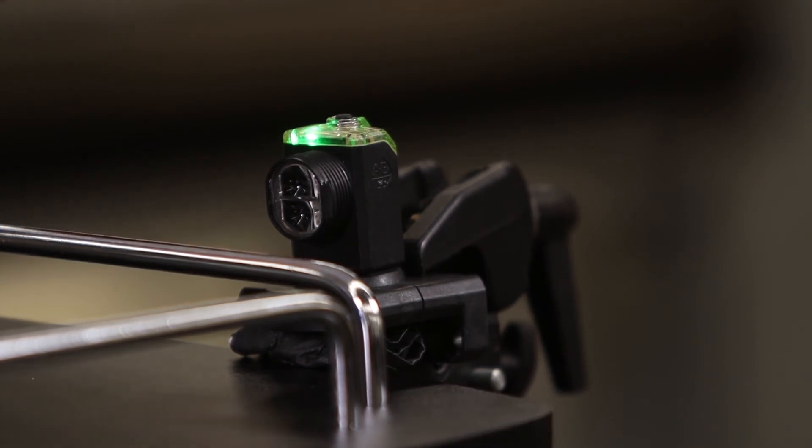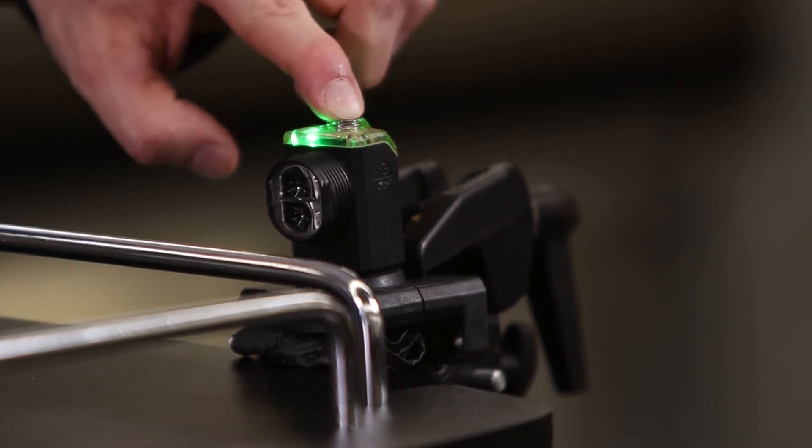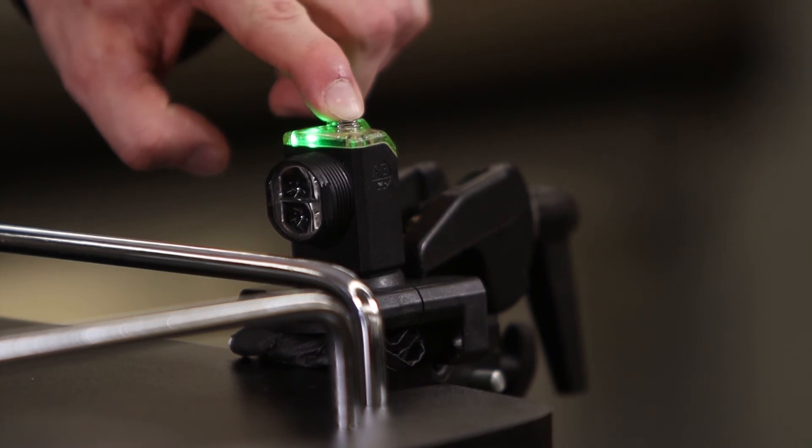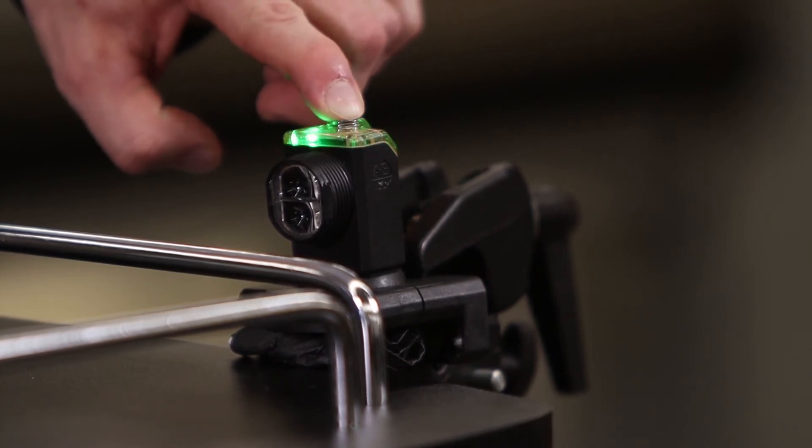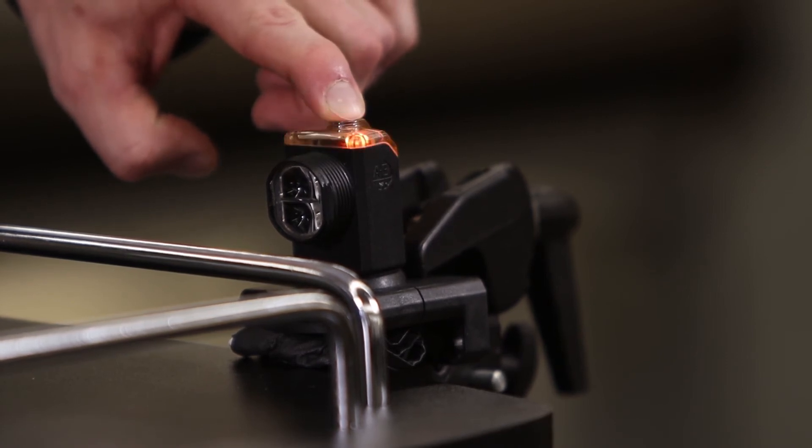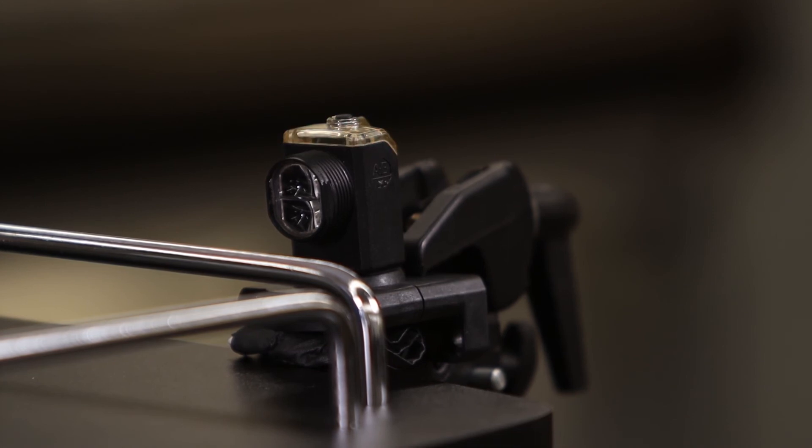To force the output type, press and hold the button for 12 seconds until the green and orange LEDs begin to flash together. Then release the button. You can now toggle from auto NPN to PNP by pressing and releasing the button to scroll through each option.